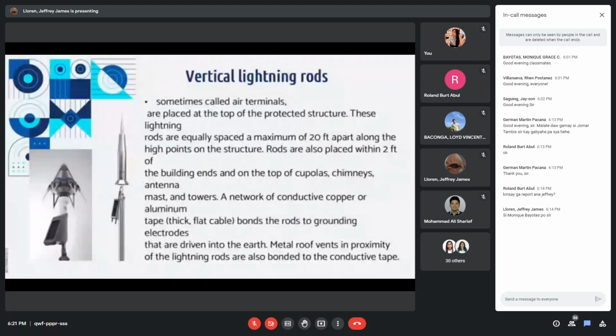So, let me continue. Sometimes called air terminals, lightning rods are placed at the top of the protected structure. These lightning rods are equally spaced a maximum of 20 feet apart along the high points on the structure. Rods are also placed within 2 feet of the building ends and on the top of cupolas, chimneys, antenna masts, and towers. A network of conductive copper or aluminum tape, thick flat cable binds the rods to grounding electrodes that are driven into the earth. Metal roof vents in proximity of the lightning rods are also bonded to the conductive tape.